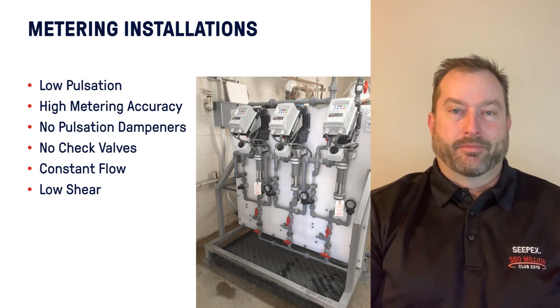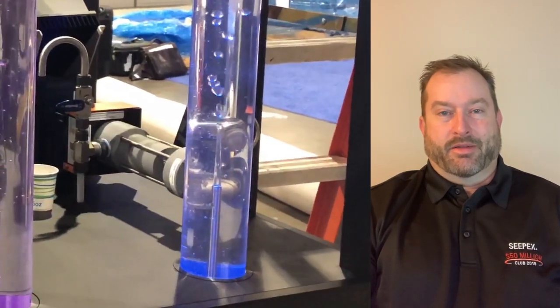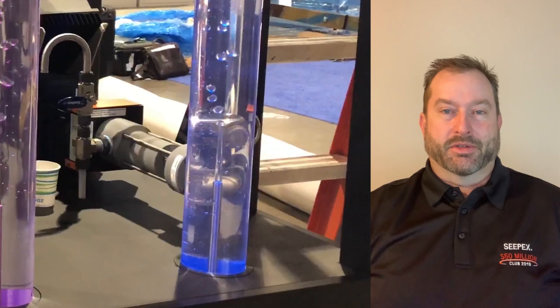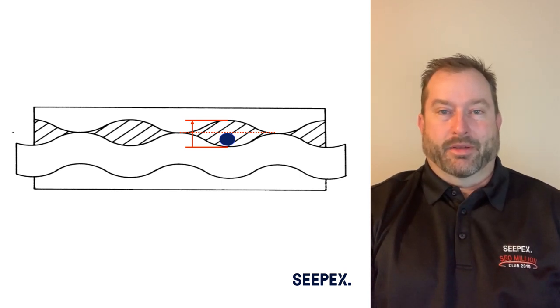These pumps are also used for metering — they're very low pulsation and very accurate, so you can actually eliminate the need for a pulsation dampener unlike a lot of competitors' metering pumps. The pump doesn't use any check valves; it acts as a valve itself due to the compression between the rotor and stator. As one cavity stops, another one is forming, creating almost uninterrupted flow with very minimal pulsations. The pump can handle large solids — over four inches on some larger pumps — and because of how the cavity is formed, when those solids are trapped in the cavity, there's very little damage.